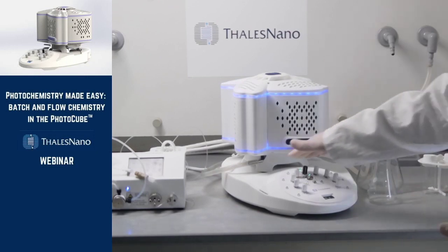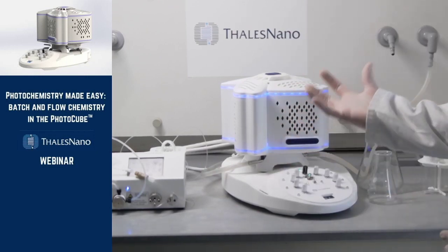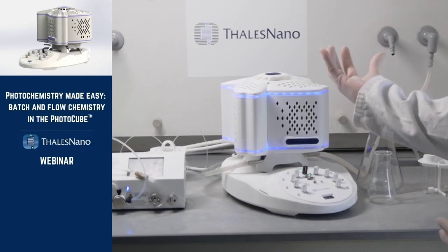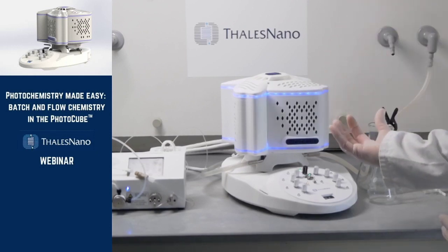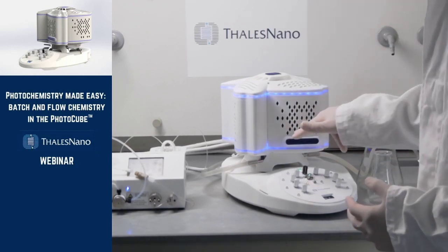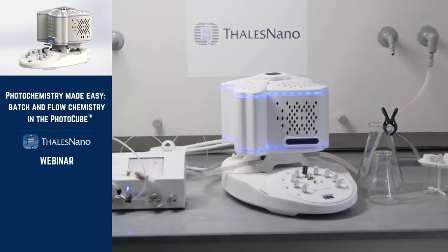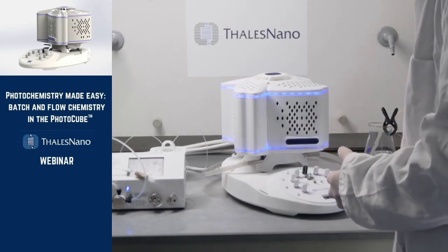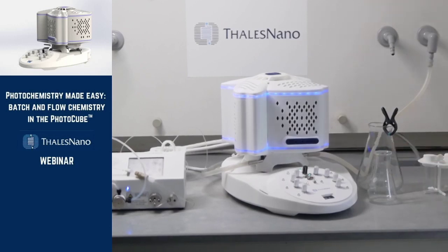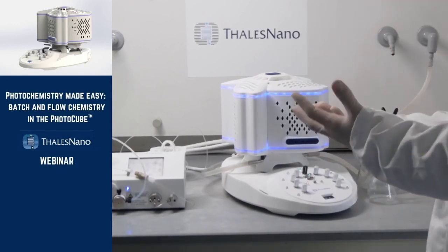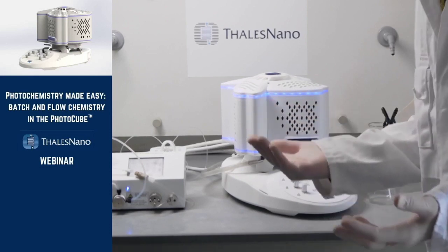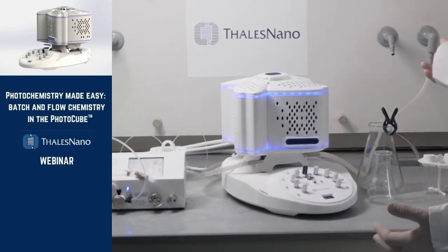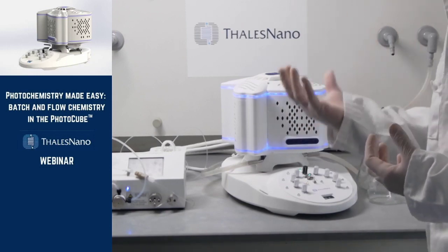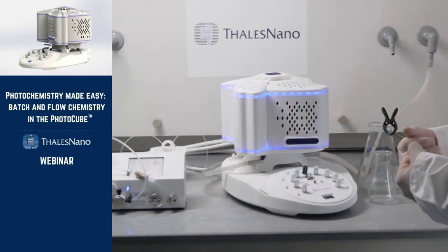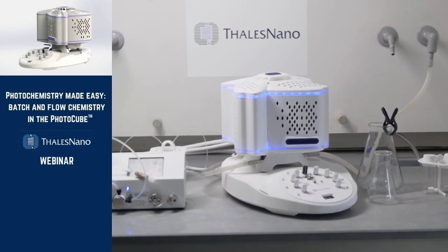The water inside cools down the photochemical reaction chamber via a fan and a heat exchanger that is at the bottom of the reaction chamber. You can also use other external cooling systems such as a chiller, not only tap water, and it may be even better if you want to control more accurately the temperature of your reaction chamber.